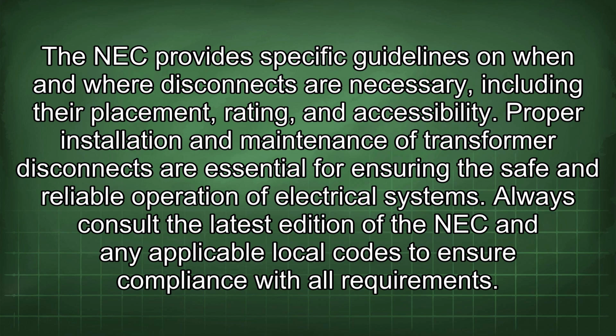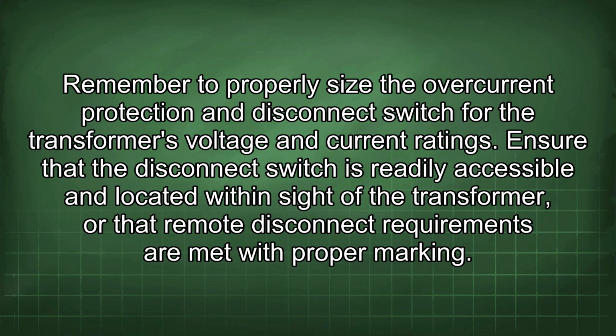Always consult the latest edition of the NEC and any applicable local codes to ensure compliance with all requirements. Remember to properly size the overcurrent protection and disconnect switch for the transformer's voltage and current ratings. Ensure that the disconnect switch is readily accessible and located within sight of the transformer, or that remote disconnect requirements are met with proper marking.